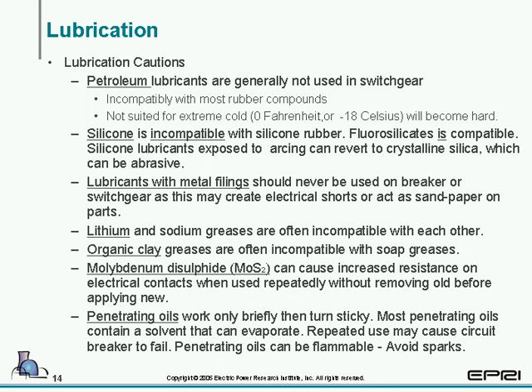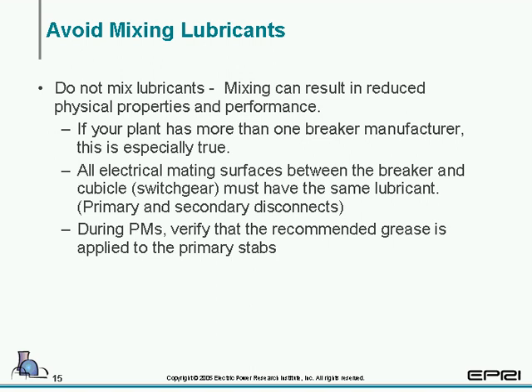And here we're just not going to actually read these, but here is a list of lubricants and some of the compatible and incompatible properties about them. And we'd like to take a look at the last one, penetrating oils. One thing that you want to keep in mind about penetrating oils is they contain solvents. So they may act as oils for short periods of time, but then the actual solvent will evaporate out. And the idea here on this slide is that you must know and control the lubricants you are using. You don't want to mix them, and if you change the lubrication you're using on the breakers, you also want to make sure that you pay attention to the old lubrication that is in the switchgear.